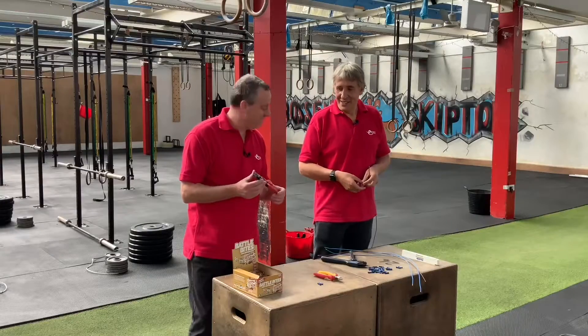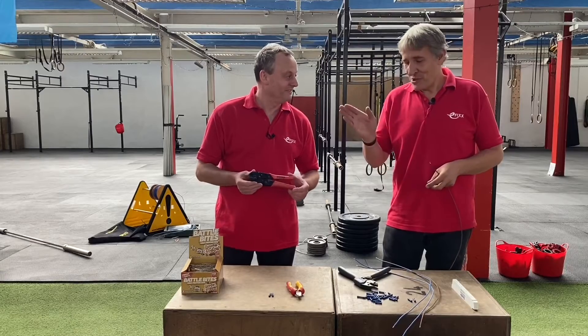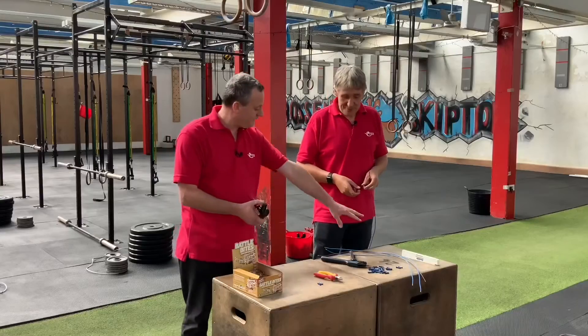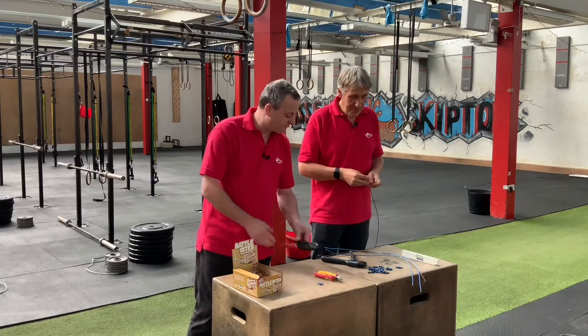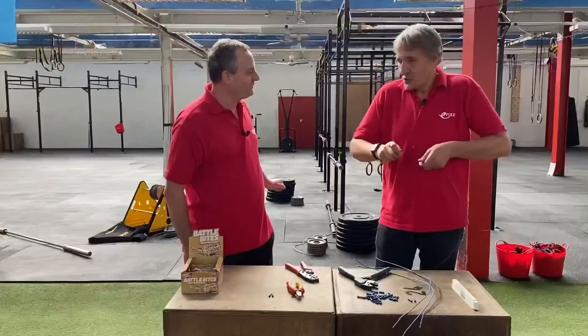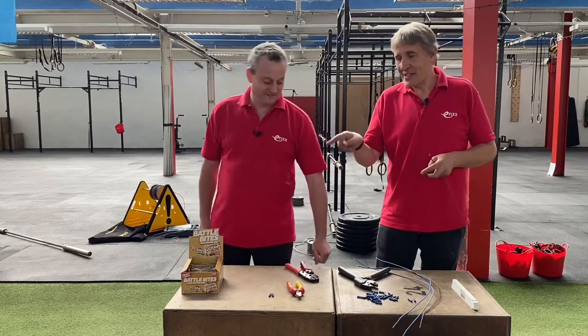I take it I've got the reasonably priced version of the tool then. You're in the red corner, I'm in the blue corner. So we're going to crimp together a couple of conductors - they're 2.5mm by the looks of things - and by the setup behind me, we're going to hang some weights from them. Let's get limbering up Gary, you're going to need that snack.